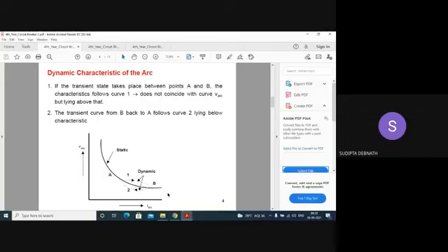But there is some deviation in the actual operation of a circuit breaker. This deviation in the nature of the arc can be explained by ionization of the arc discharge, because ionization is responsible for the maintenance of the arc. So its intensity actually determines the magnitude of the current. If the current increases suddenly, a certain time lapse is necessary before the state of ionization adapts itself to the new conditions. Hence, as the current increases, ionization always corresponds to the current which was previously flowing through the arc. Because even if the current increases, the ionization will not increase instantaneously.